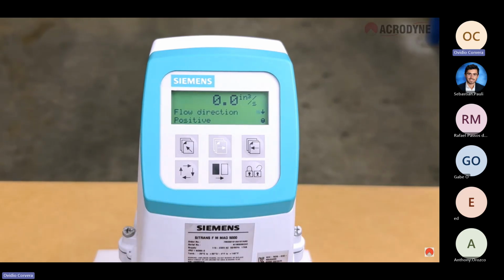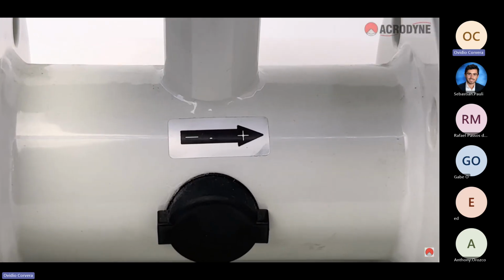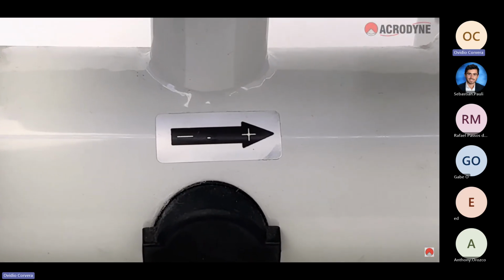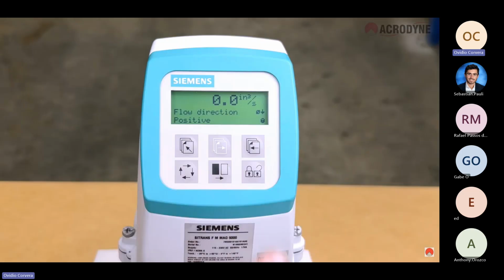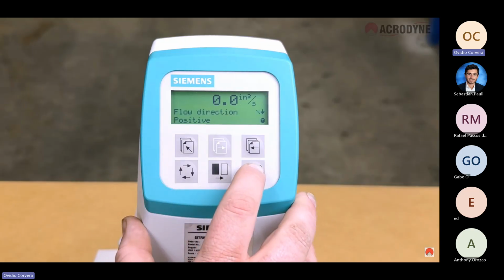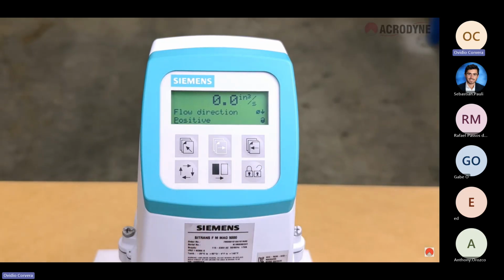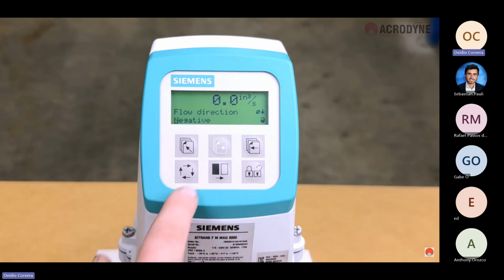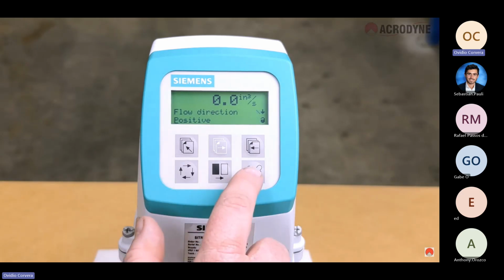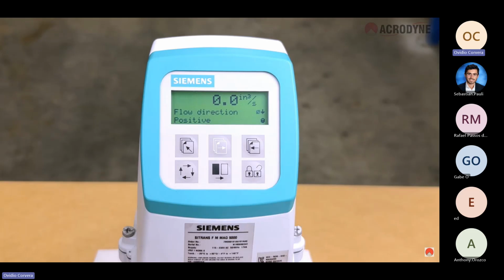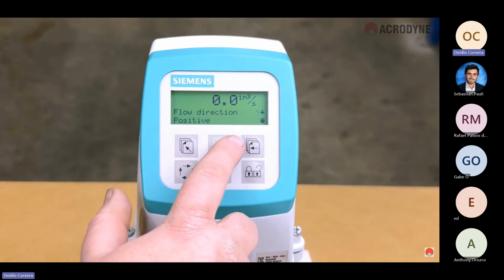Flow direction. The default setting for the flow direction is positive. This means that the flow through the sensor is in the same direction as the arrow marked on the front flow sensor tube. If the flow is in the opposite direction of this arrow, choose negative. If this needs to be altered, then press the lock-unlock key and press the change button to choose the appropriate setting. Press the lock or unlock key again to save the desired setting. If this does not need to be altered, press the forward key to the next parameter.